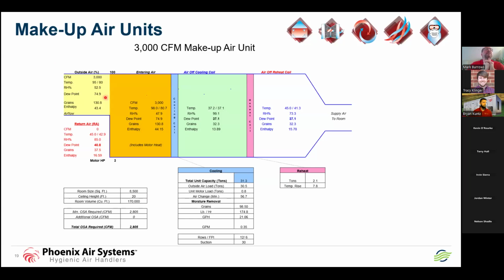So we take the yellow at the outside air at 95/80. Why is there a color change? Because we've got the motor heat. We take the air from 95 degrees up to 98, so there's that 3-degree rise. The air off the cooling coil in this case is 37.2, 37.1. Notice again the relative humidity, 99.1. So now we're talking worker comfort.